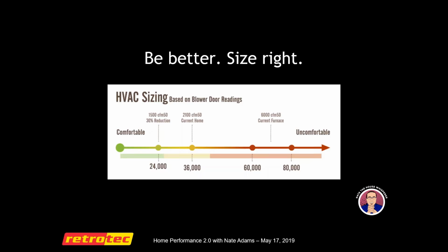So what you're looking at here is a house, a 2,000 square foot house in Rochester, New York. The house actually had a 2100 blower door result, which worked out to right about a 3-ton heat load. That's a 3-ton heat pump or a small furnace, like a 40,000 BTU modulating furnace, something like that - the right piece of equipment for where that house was.